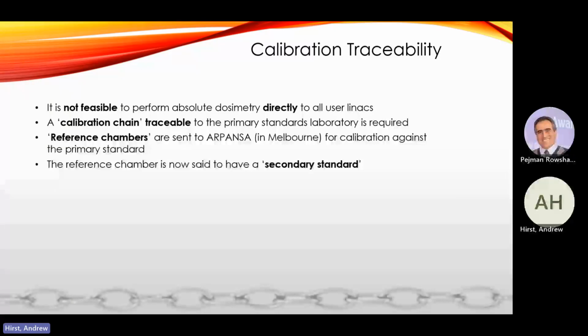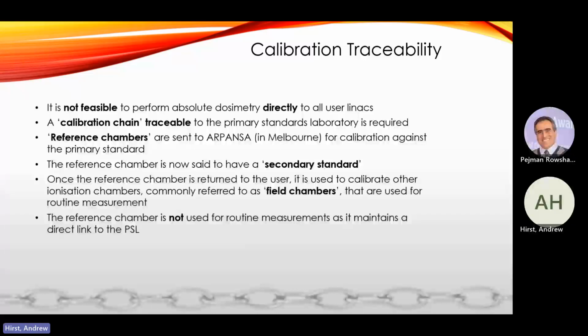That reference chamber is now said to have the secondary standard, so we transfer that across from the primary one. Once that's returned back to us at the hospital, we use it to calibrate all of our other ionization chambers. So we don't use the reference chamber for routine measurements. It maintains that direct link to the primary standards lab, and we don't want to break it and lose our connection to the primary standard. Also, we want to have a lot of different ion chambers that we can take measurements with. So we do what's called a cross calibration and transfer the standard again to a field chamber.